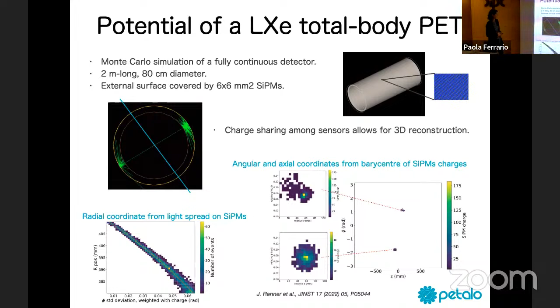For the third coordinate, which is the depth of the interaction, so the radial coordinate, what we do is to exploit the light spread on the silicon PMs. In fact, if the event that happens is closer to the silicon PM, the light spread is smaller. Otherwise, it's larger. It is an almost linear relationship, so it is very good to extract the position in the radial coordinate. So the results that we found for the spatial resolution are 1-2 millimeters full width at half maximum for events that deposit all their energy in one point, which are photoelectric events, which are the ones that give you a better reconstruction of the line of response.